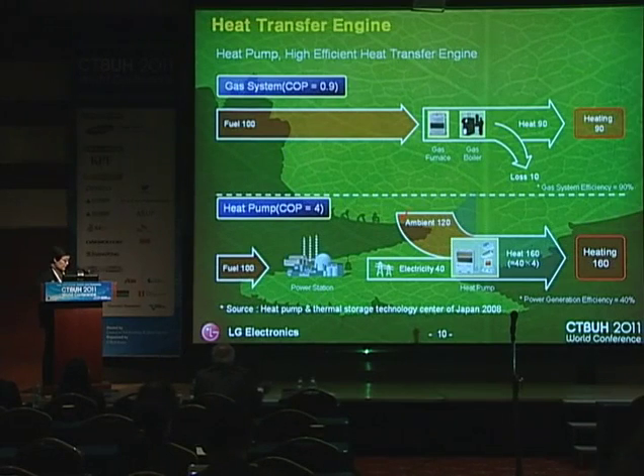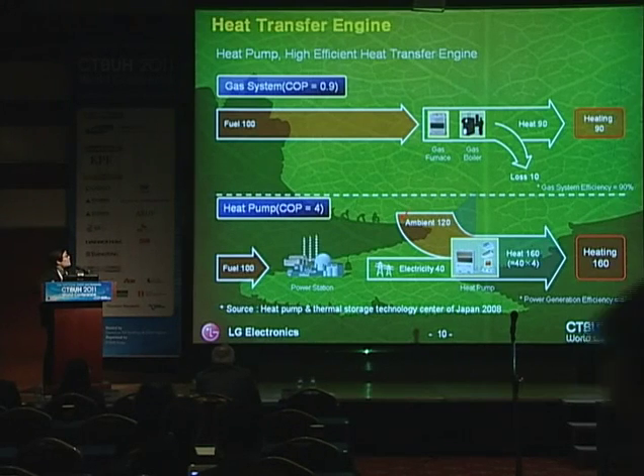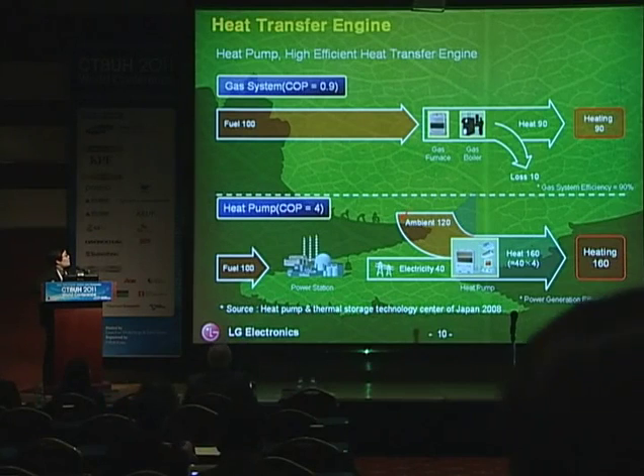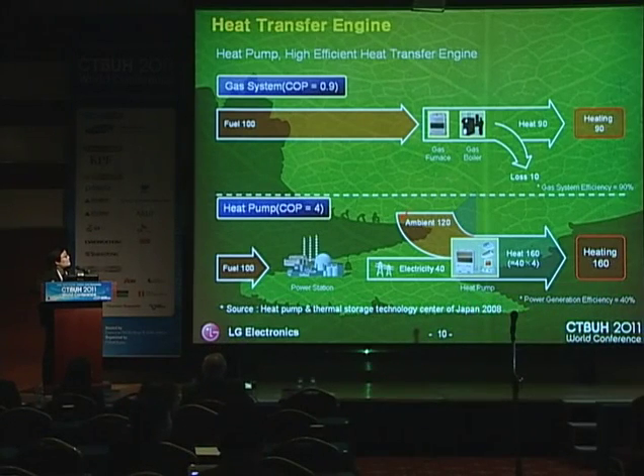Now I want to describe the efficiency of the heat pump. A heat pump produces four times the heat as its input electric energy. If you want to make heat, you have a boiler and a heat pump. If you have 100 units of fuel and use a boiler for heat, you make just 90 kilowatts of heat, because 10 kilowatts of heat is lost.